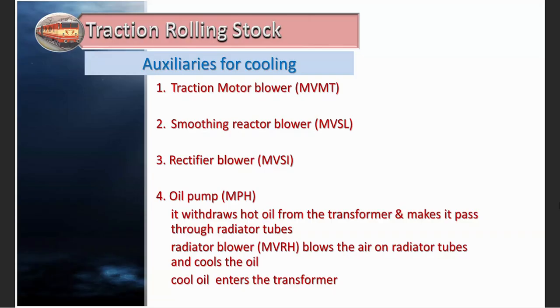It's a closed system. It means that the transformer oil does not come in contact with the external environment, and this is required so that the transformer oil does not absorb moisture. Any absorption of moisture will reduce the breakdown voltage and the transformer may break. The other function of the oil pump is that it ensures that the temperature of the transformer oil does not go above the flash point of transformer oil, which is anyway very high.